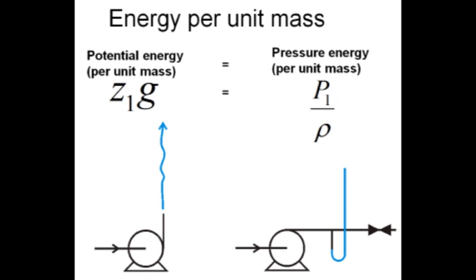If instead of having the pump pumping vertically upwards, we were to have it horizontally and put a valve on the end of it—not necessarily fully closed but certainly one that we can open or close—then that would generate a certain amount of pressure or pressure head on that discharge side of the pump, which we could measure by the manometer shown there in blue on that right-hand diagram. Again, that would be a certain height of liquid that would represent the pressure in that line.